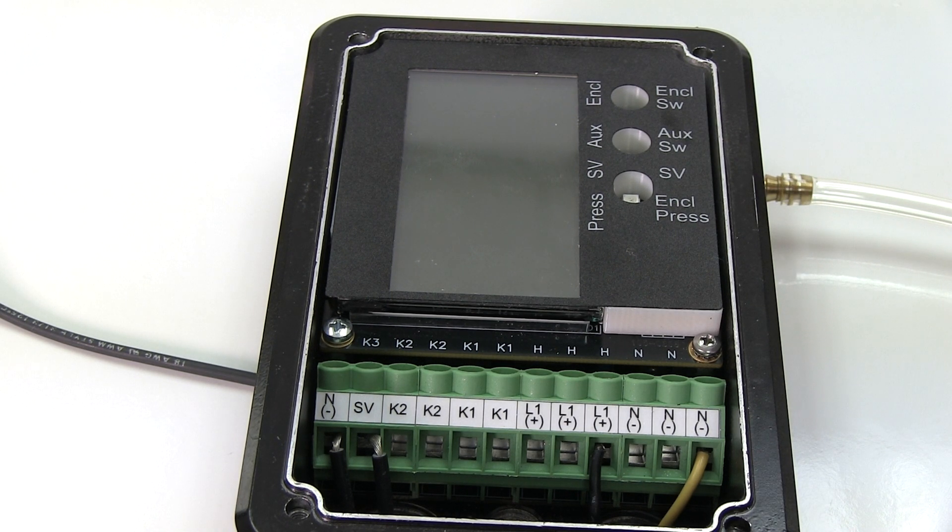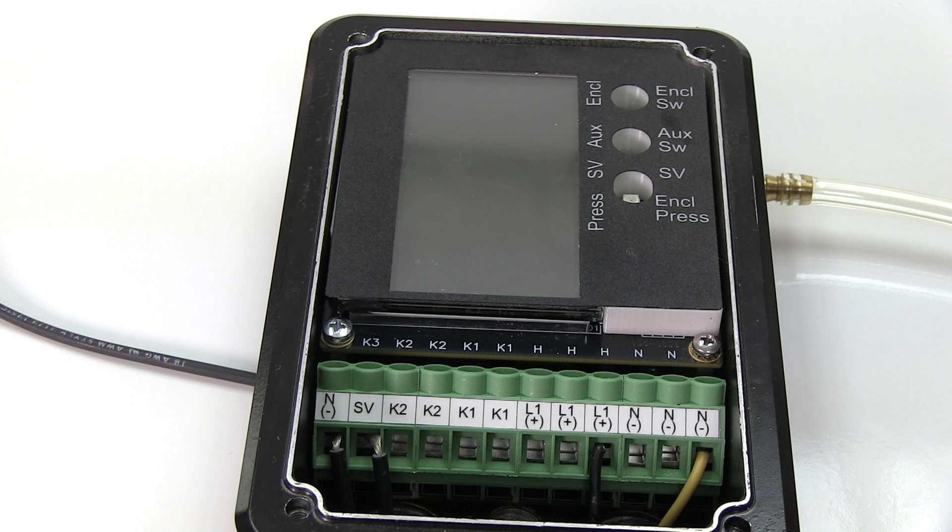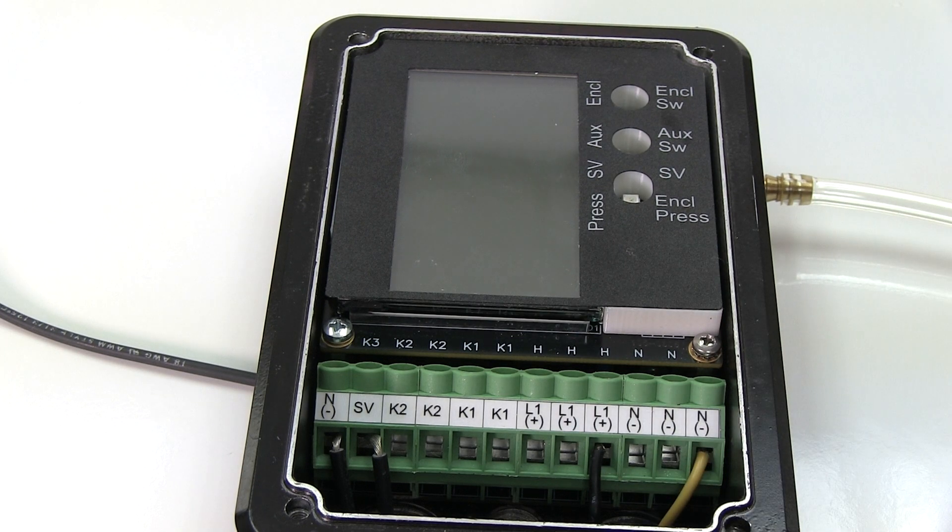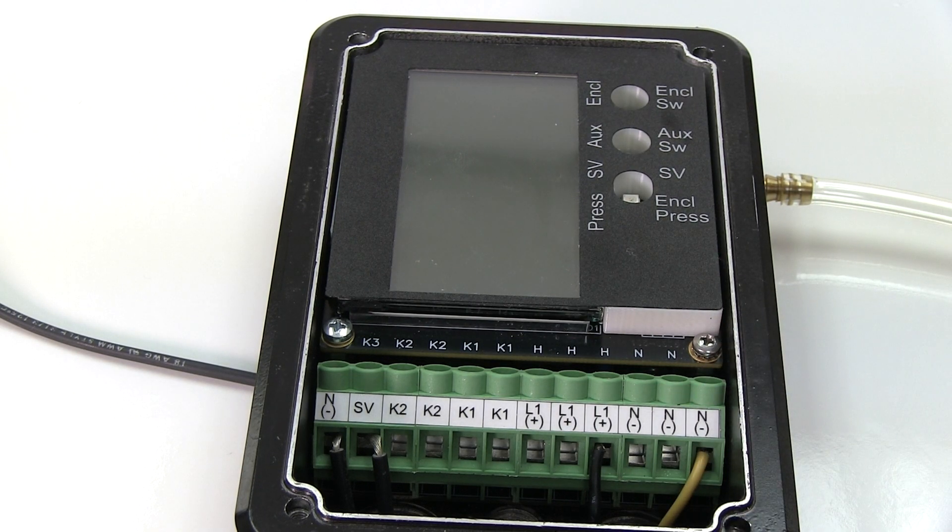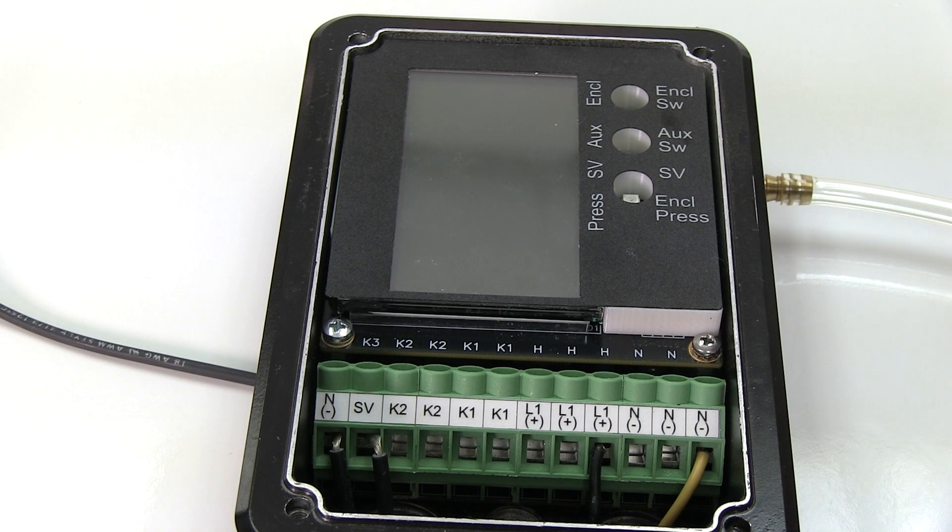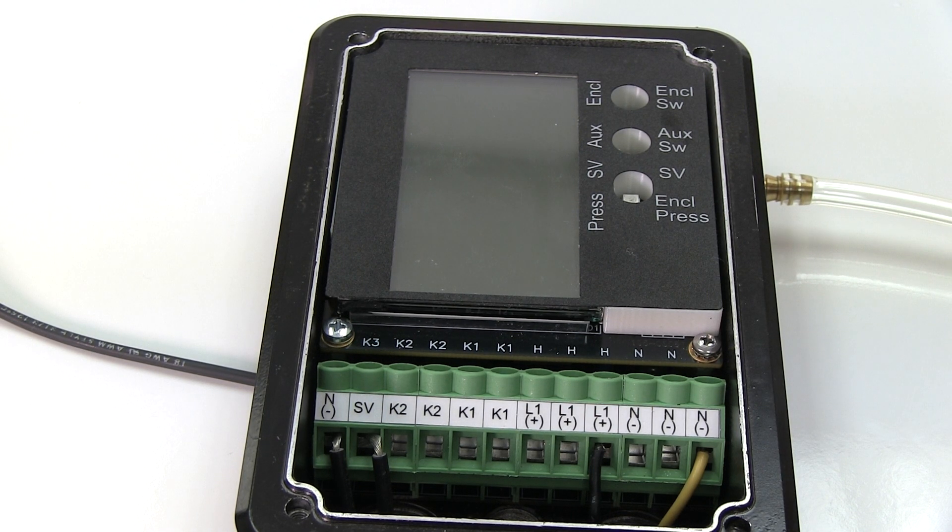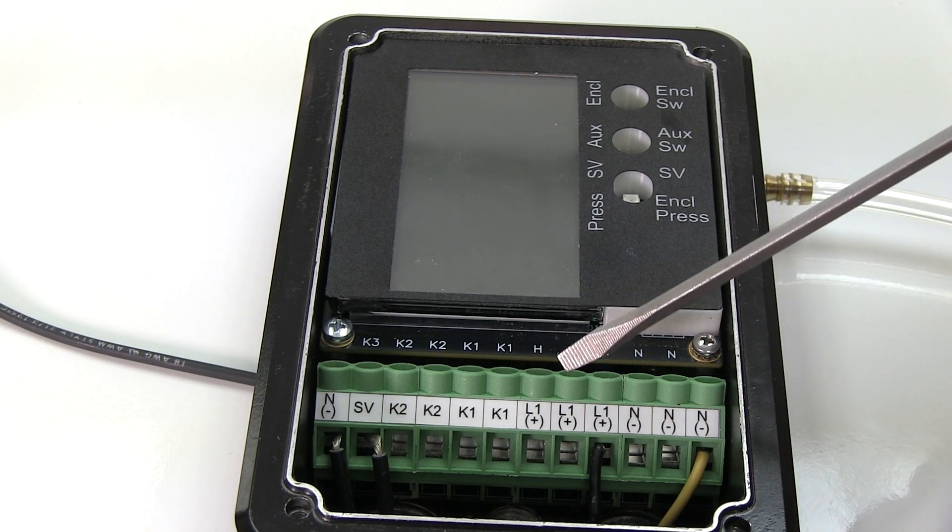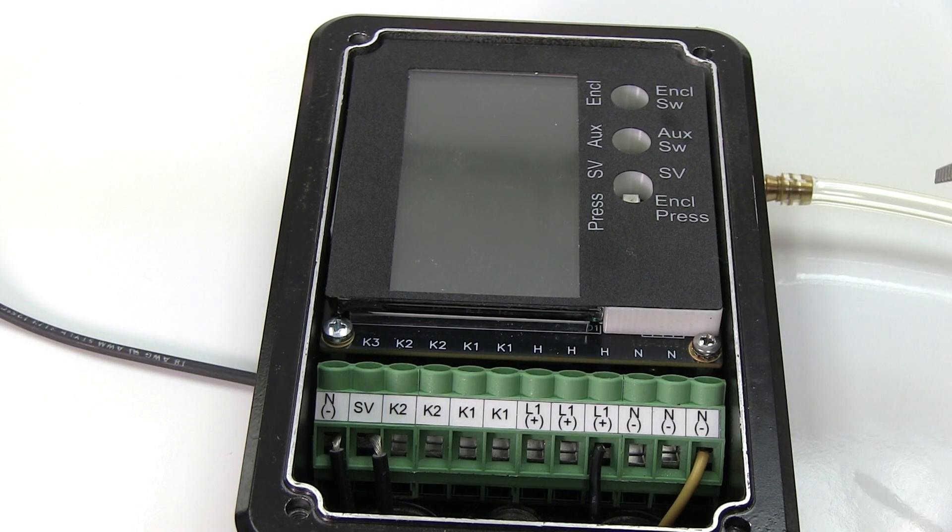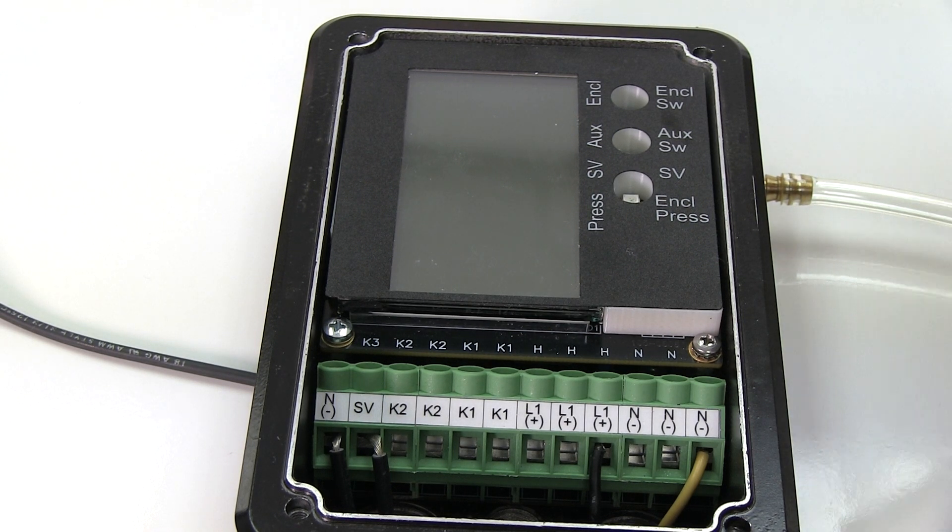Now you can bring in a separate power source. If you need 24 volts DC but you're powering the control unit with 120 and you don't want to jump it over, you can do that. You can bring in a separate power source to energize your enclosure. Or let's say if you have 480 volts going to your enclosure, you can control a contactor block with the K1 contacts. So when the purging cycle completes, K1 contact closes, energizing the contactor block and then allowing 480 into your enclosure.